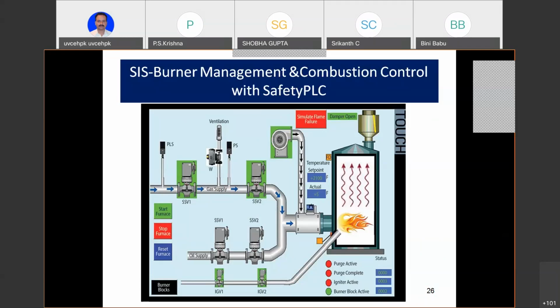But here, what is the danger? The danger is any fired gas heater. This is a heater firing, and that heat is going to heat something else. You don't worry about that; it may be water, a boiler, or some other hot oil. But in this particular heating, if the fire is not extinguished properly, and the gas is building up, and the gas or the fuel oil is ratioed so that the optimum mix is mixing and going away, heating, if it is resident there and gets into an odd combination, you could get an explosion.